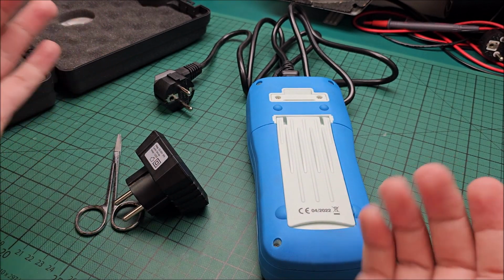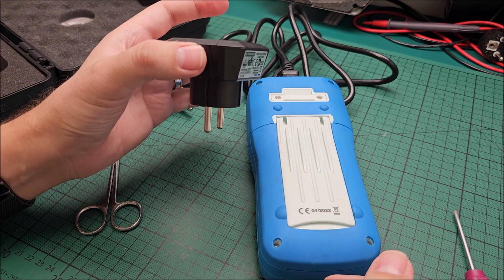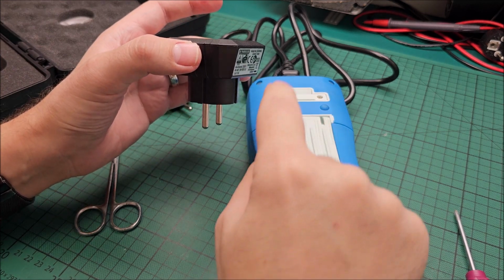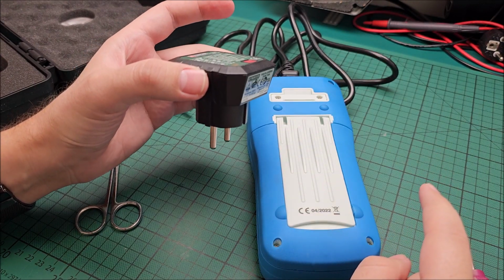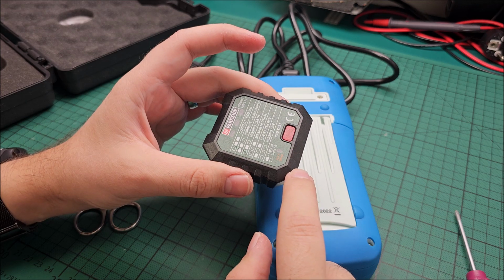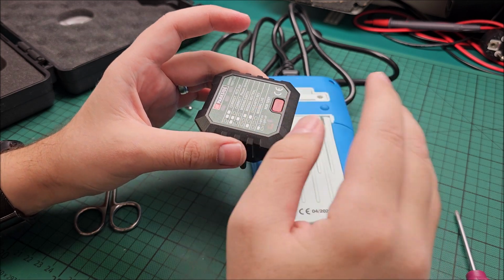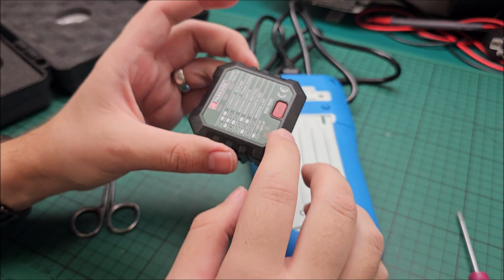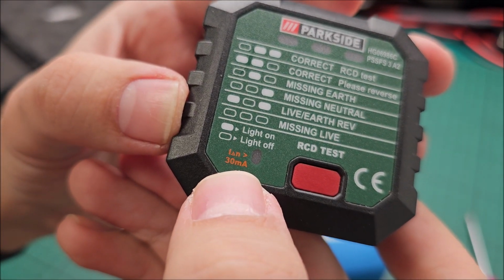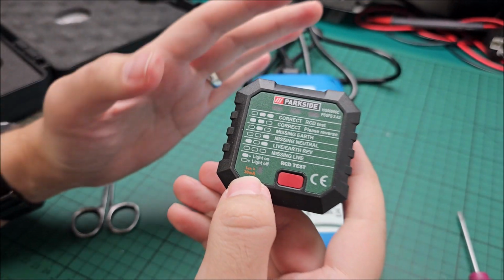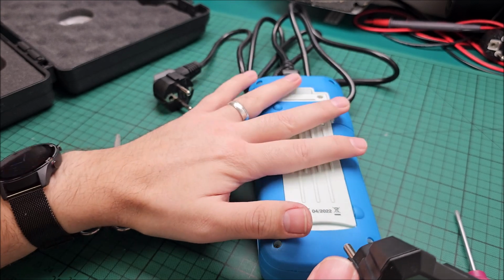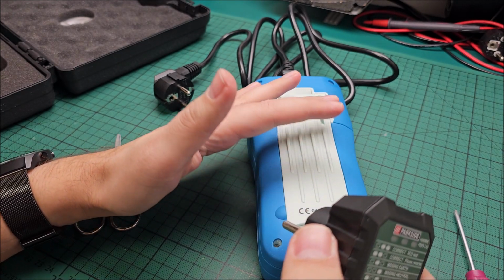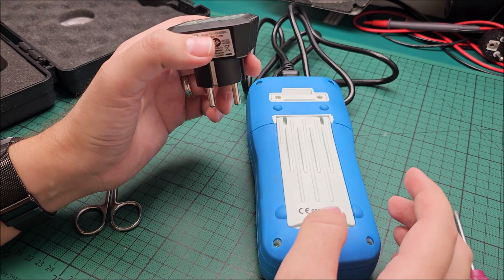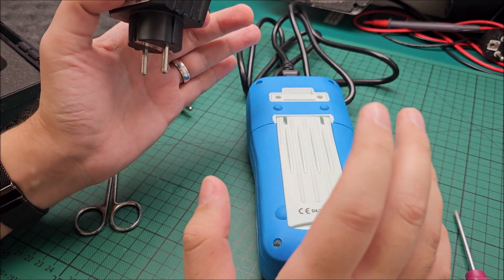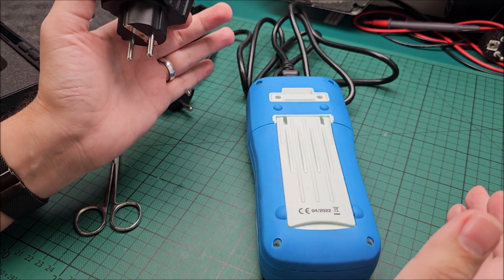we don't know. So my only logic would be that there's a difference in tripping time between the two, and the 30 milliamp one actually has a shorter tripping time, and it actually manages to trip before the other one, because this thingy doesn't know to test at less than that. So what I want to do with this is test at 20 milliamp. So the 30 milliamp should not trip, and then we should only see the 10 or 15 milliamp trip, if it makes sense to you.